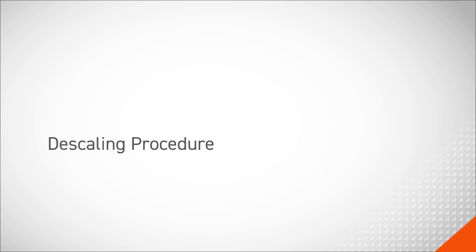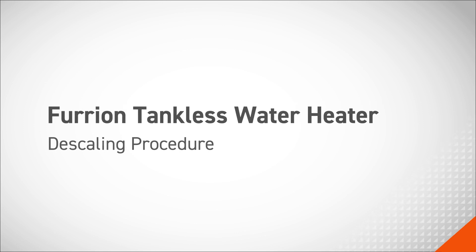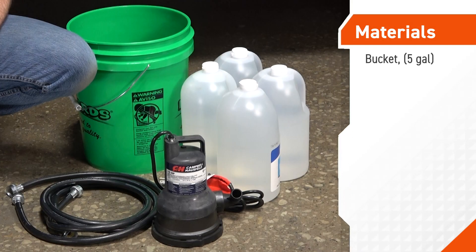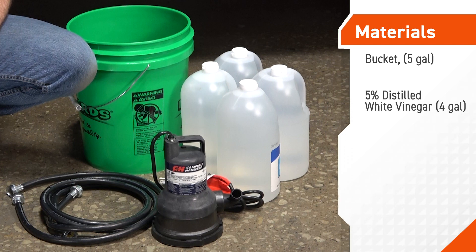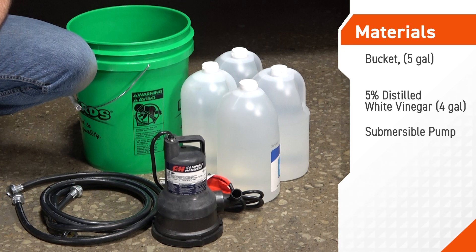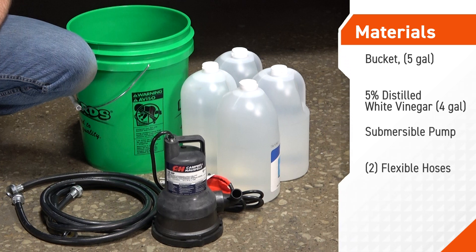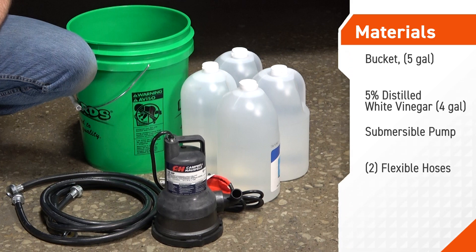In this video, we'll cover the descaling procedure for the Furrion tankless water heater. The materials required to perform this procedure include a five-gallon bucket, four gallons of 5% distilled white vinegar, a submersible pump, and two flexible hoses with one-half inch NPT female connections on either end of each hose.